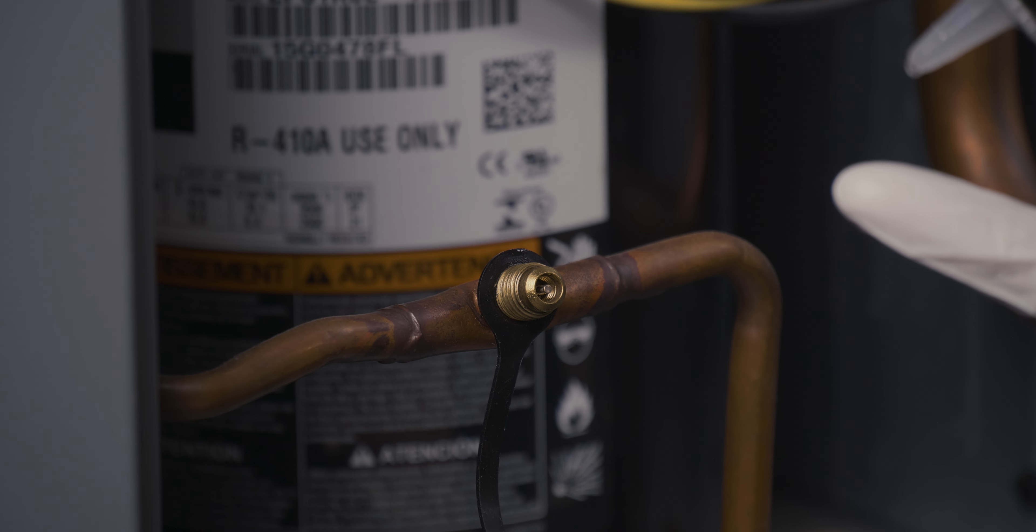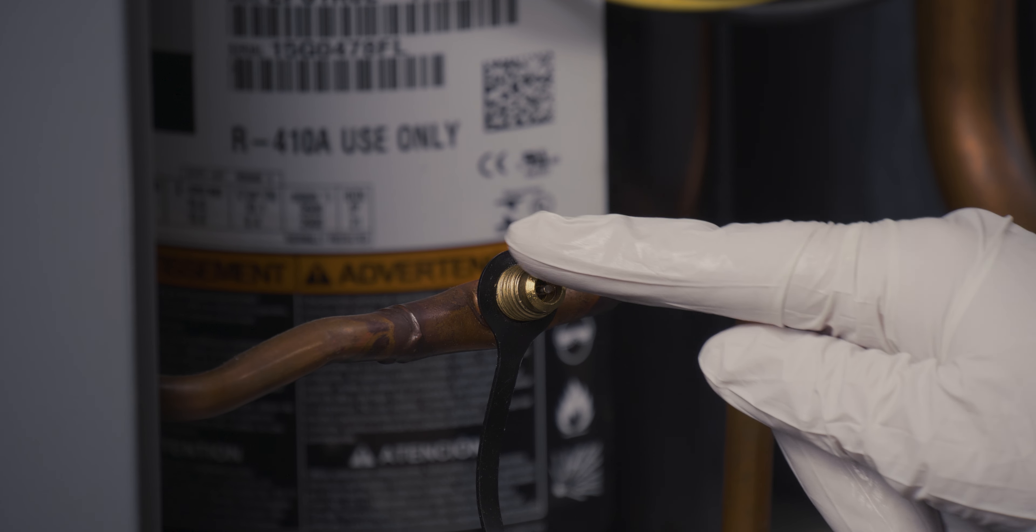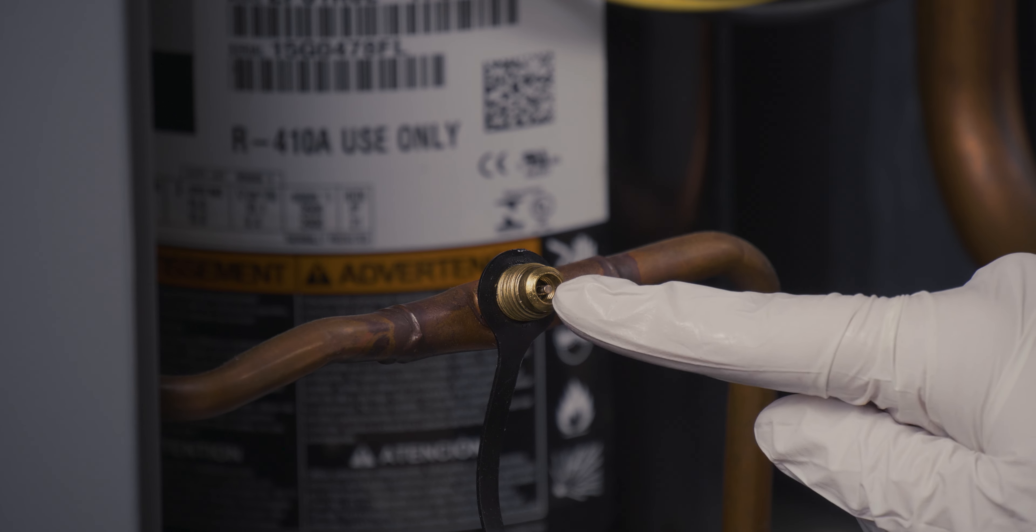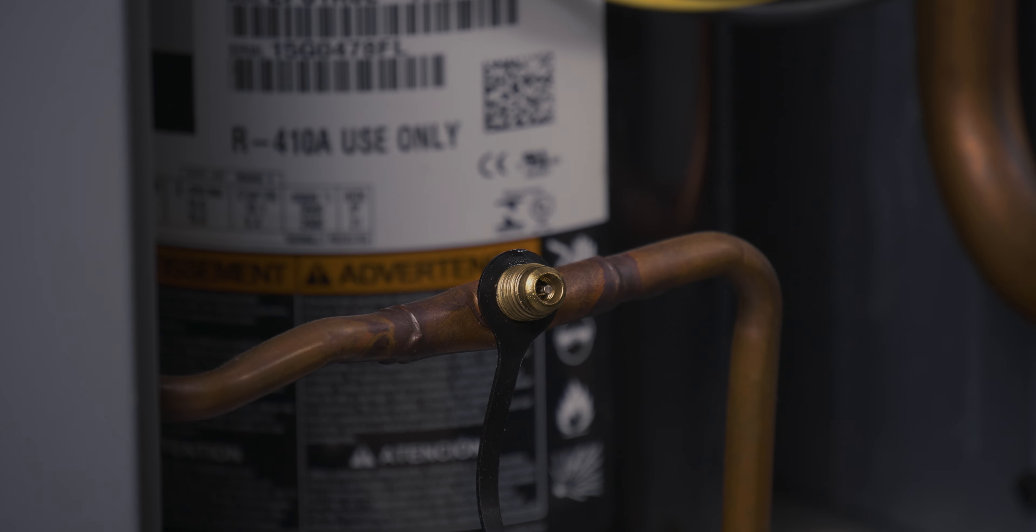When connecting the tool to the system or connecting additional tools to the charging tees access ports, always start by adding a drop of clean vacuum pump oil to the port sealing surface and hand tighten the swivel fitting.